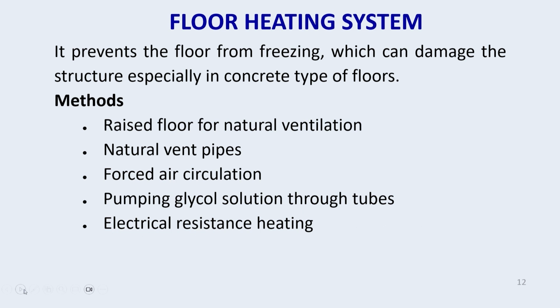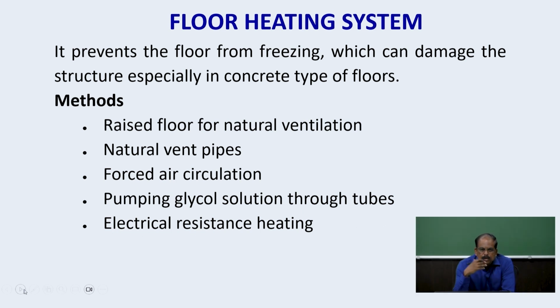Next one is the floor heating system. It is a very important component when the cold store is designed. It prevents the floor from freezing. There should not be any formation of ice or frost. If there is freezing, there are chances of the structure getting damaged, especially when we have concrete floors.